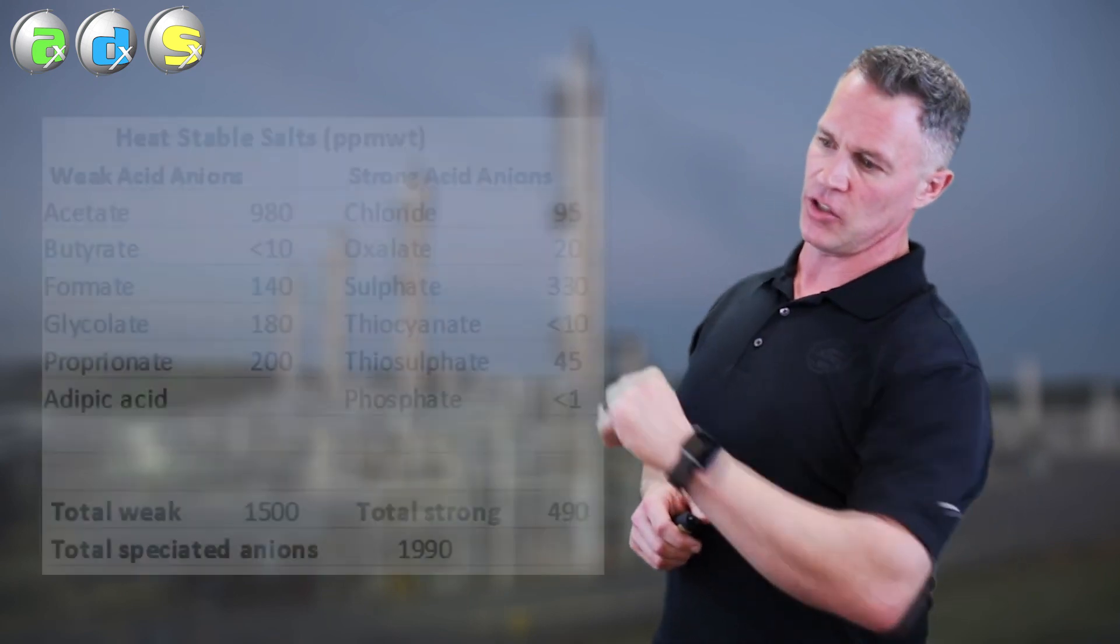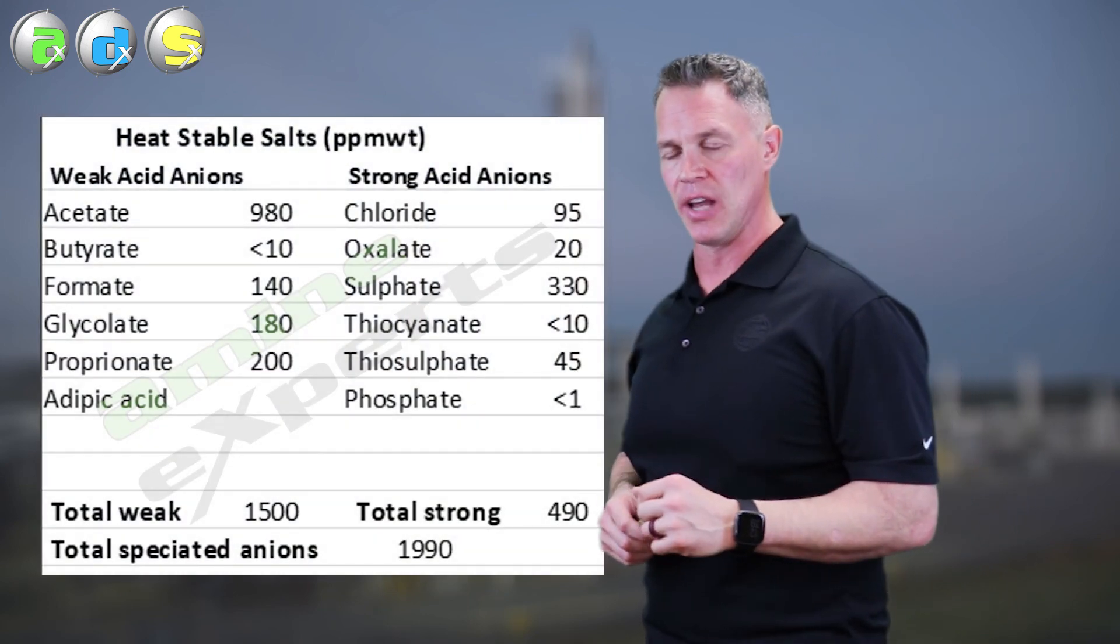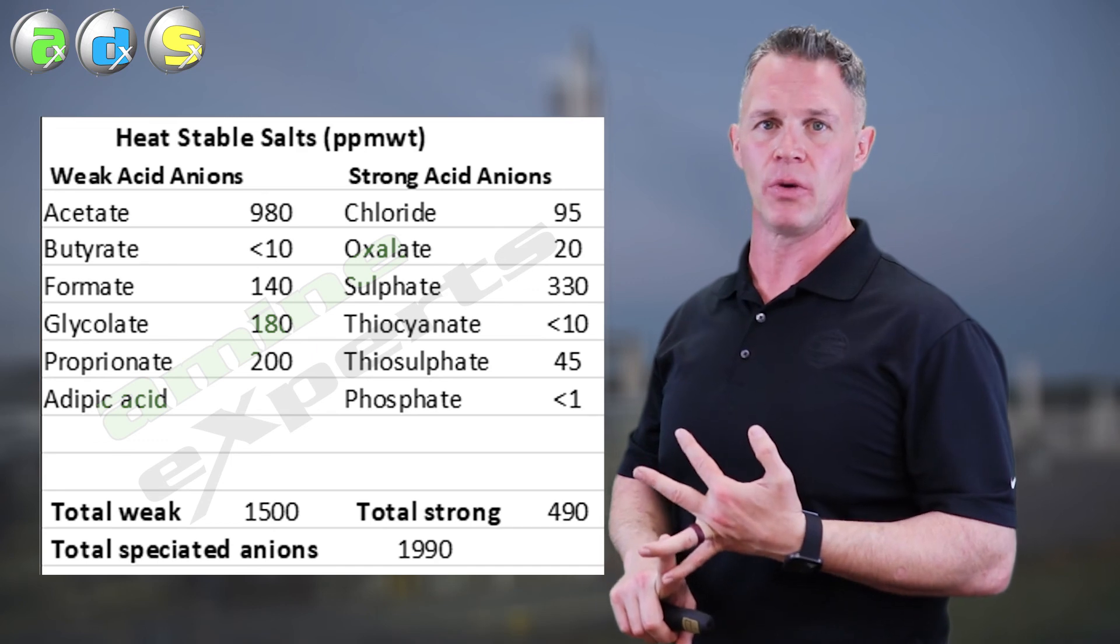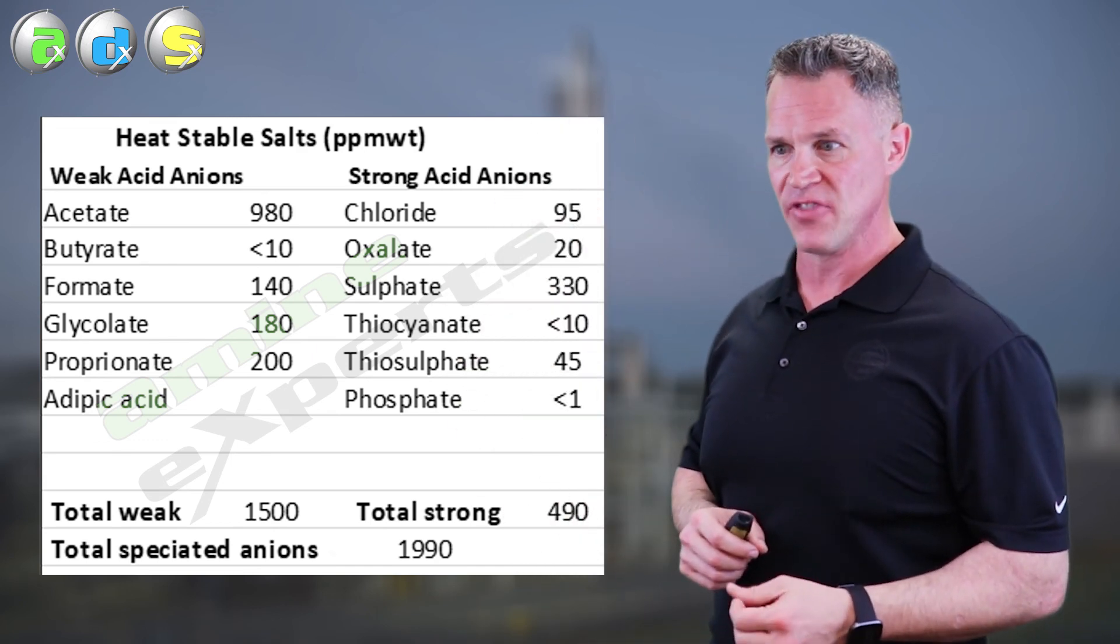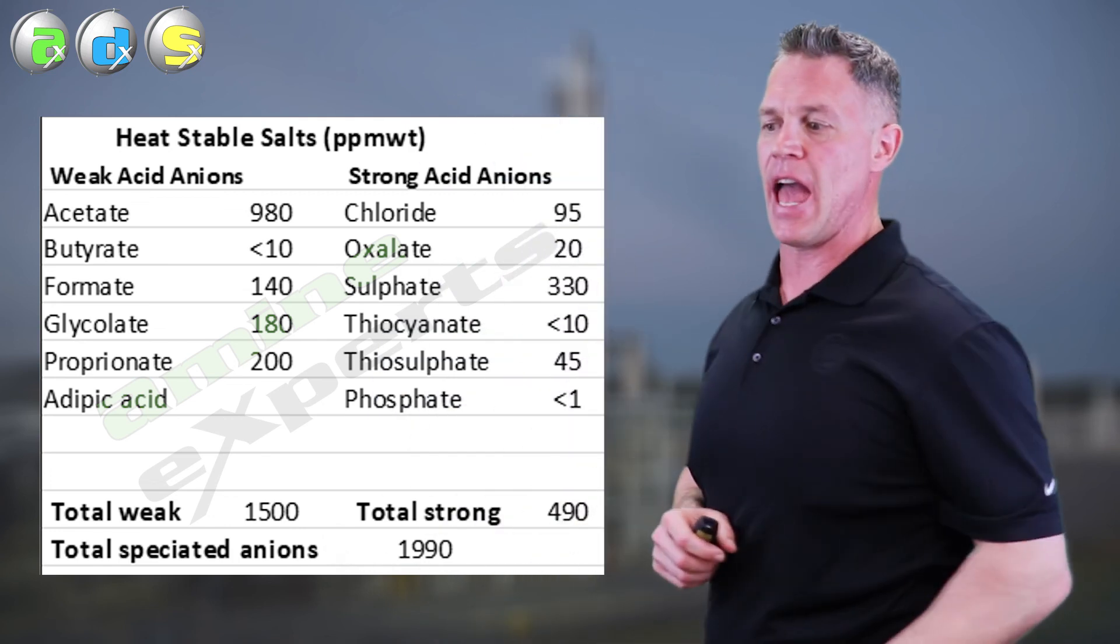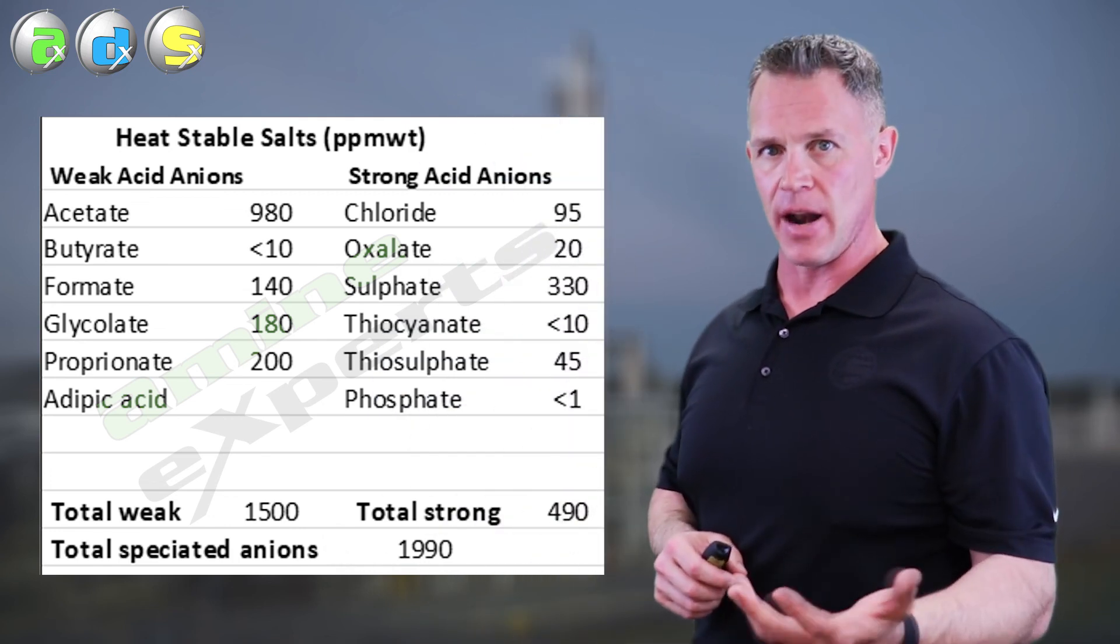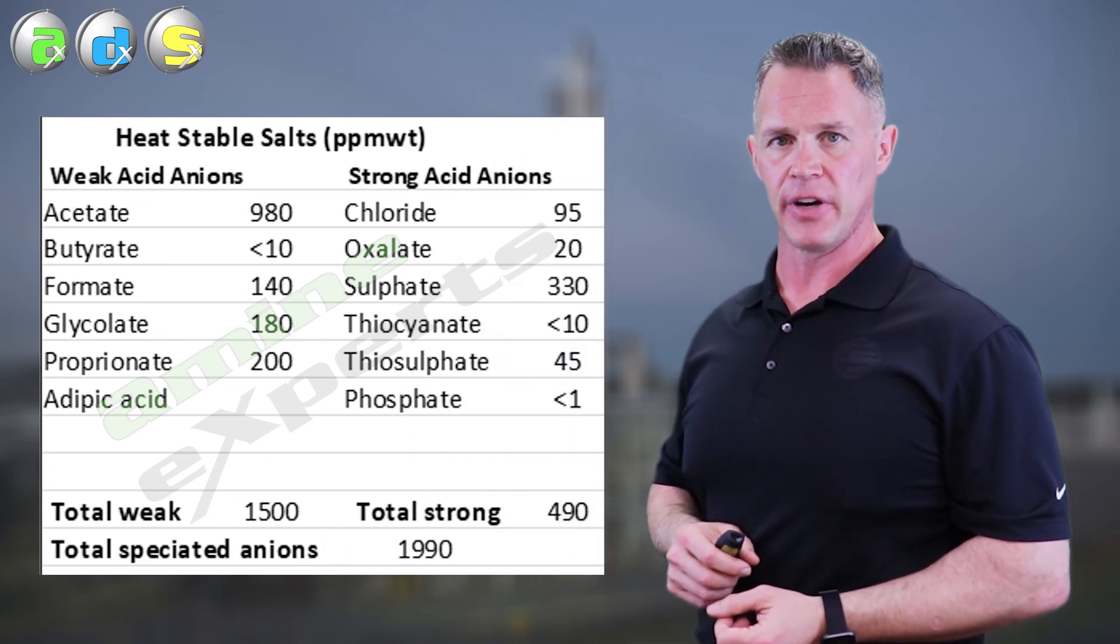And so what you do there is you get one of these amine analyses done by your vendor or by us or whoever can break out heat stable salts in their ion chromatograph. You just add up all of the anions and you don't want that number to be above those specified limits.